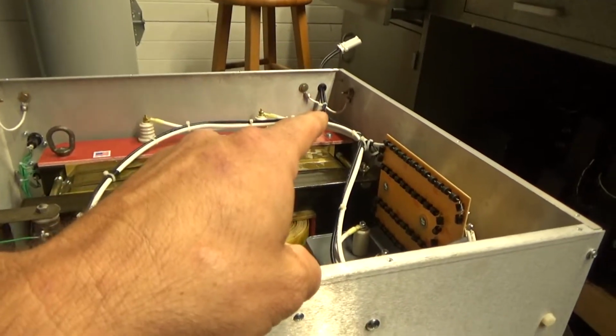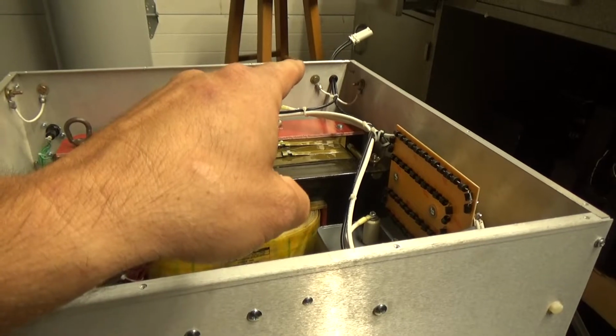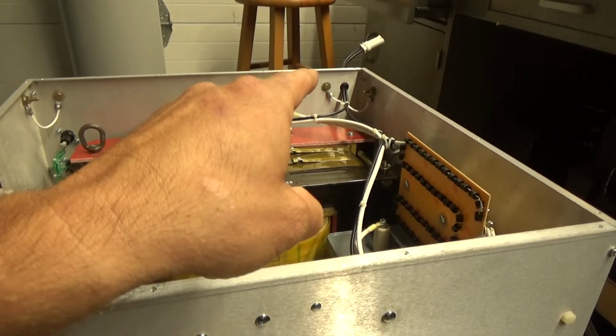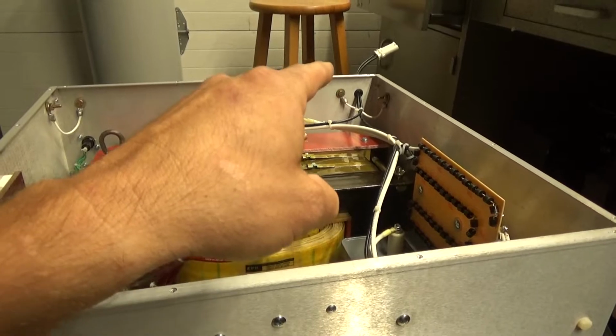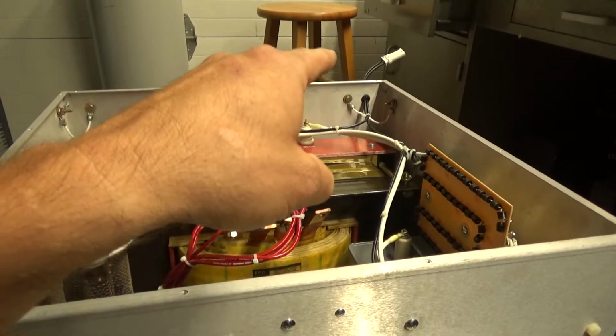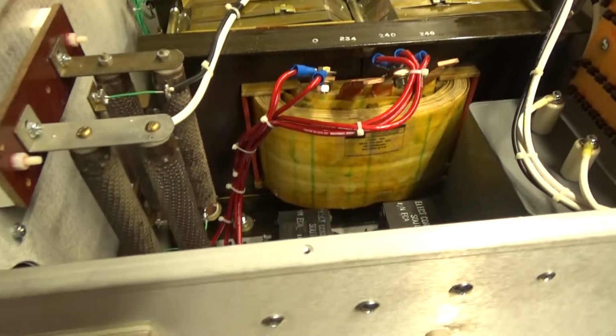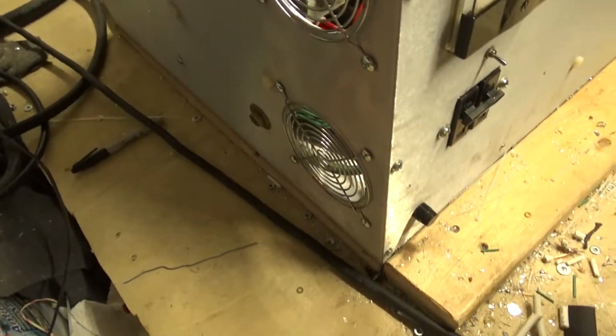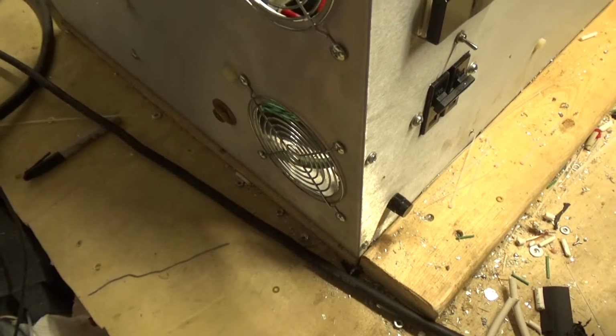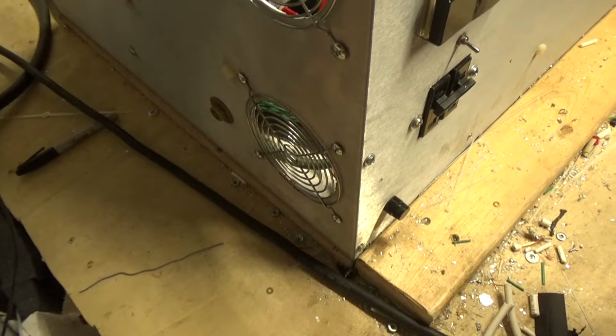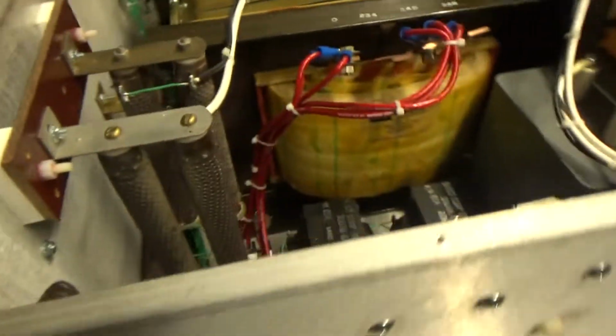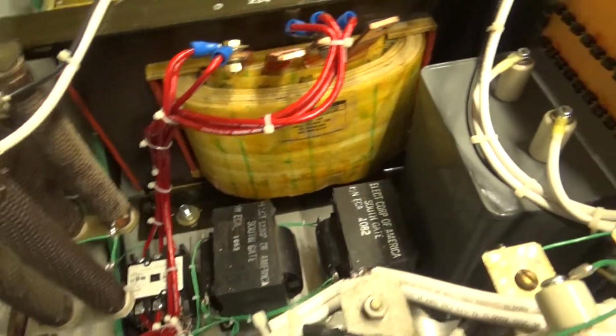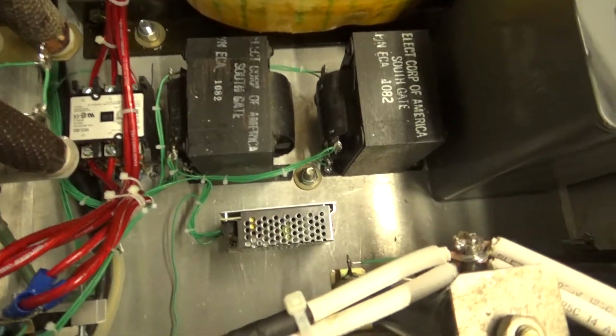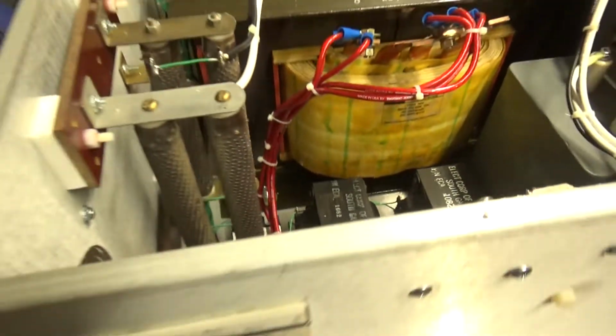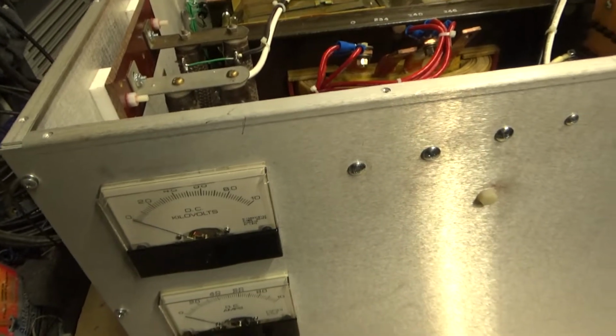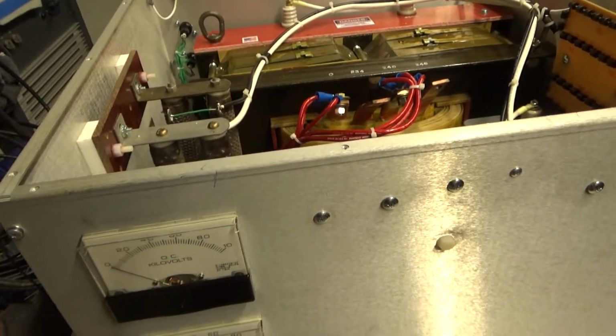I also grounded the panels together with number 10 Teflon, silver plated, stranded wire. I used grade 8 hardware. Oh, another thing, just wanted to point out -- this cabinet is reinforced with 3/4 inch 6-ply wood. I used 1/2-inch carriage bolts to hold the transformer in place, and then 7/16 carriage bolts, one there and one in each corner. The customer is going to put it on a steel reinforced dolly, so I had to slide this transformer, and it was so heavy.